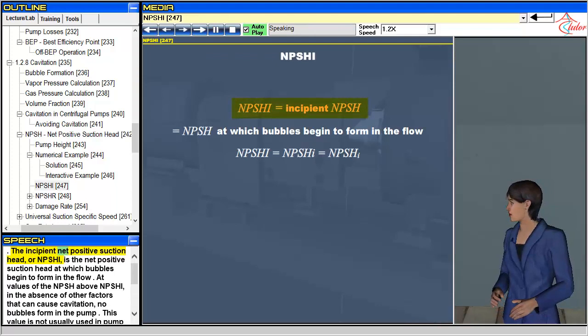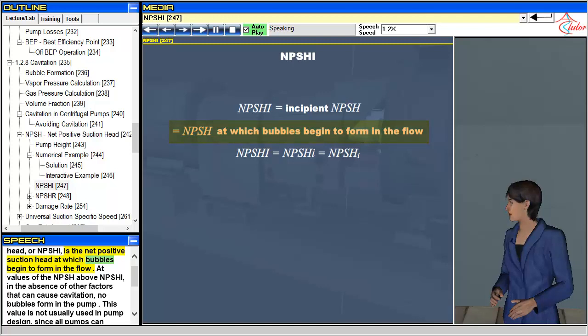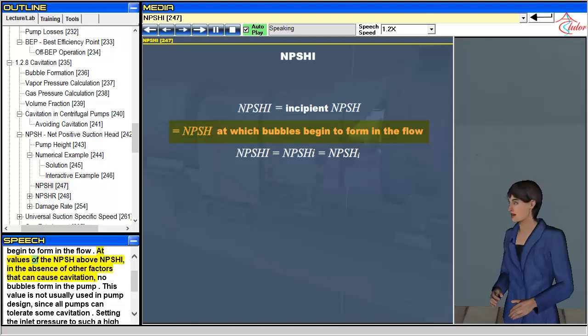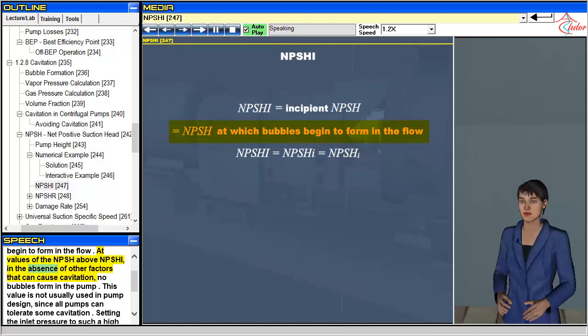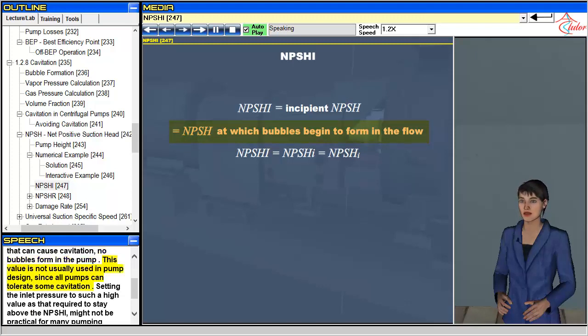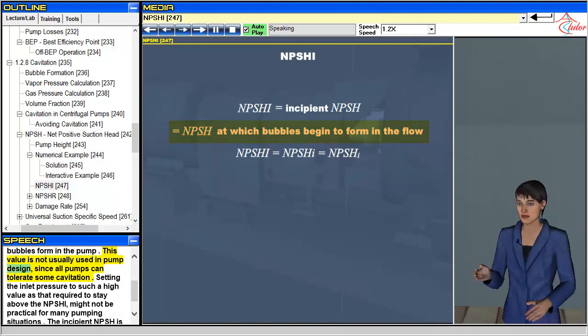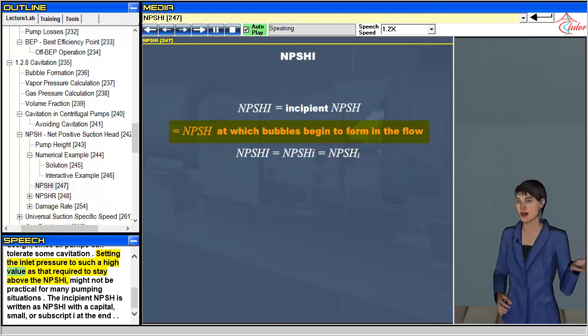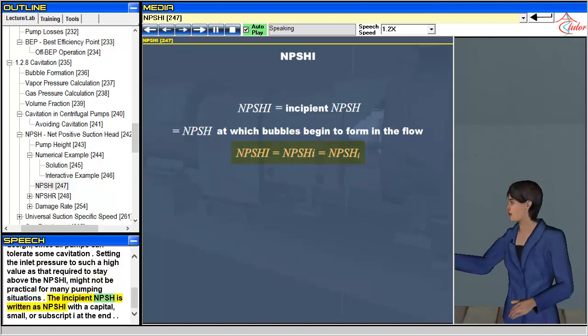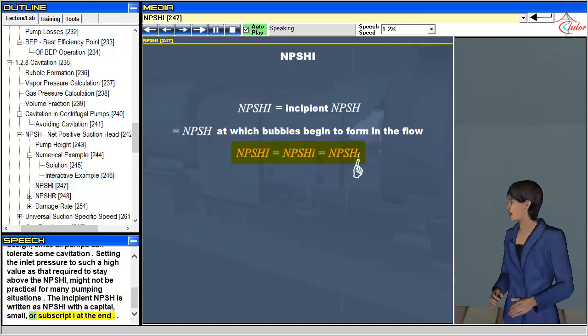The incipient net positive suction head, or NPSHI, is the net positive suction head at which bubbles begin to form in the flow. At values of the NPSH above NPSHI, in the absence of other factors that can cause cavitation, no bubbles form in the pump. This value is not usually used in pump design since all pumps can tolerate some cavitation, and setting the inlet pressure to such a high value as required to stay above the NPSHI might not be practical for many pumping situations. The incipient NPSH is written as NPSHI, with a capital or subscript I at the end.